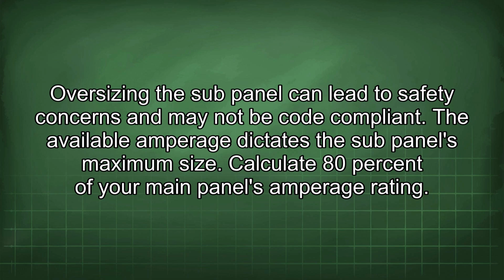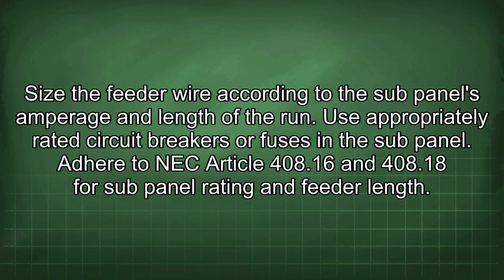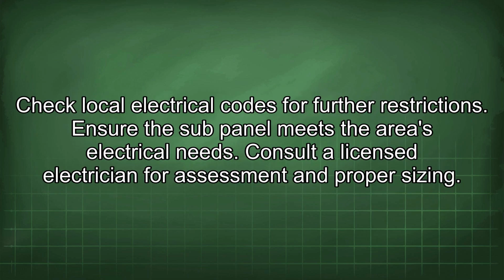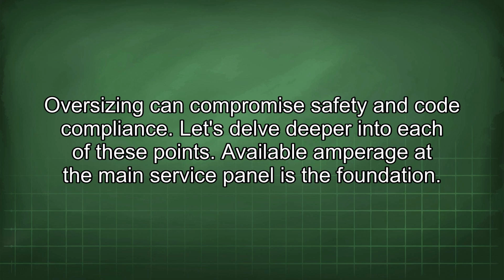The available amperage dictates the sub-panel's maximum size. Calculate 80% of your main panel's amperage rating. Size the feeder wire according to the sub-panel's amperage and length of the run. Use appropriately rated circuit breakers or fuses in the sub-panel. Adhere to NEC Article 408.16 and 408.18 for sub-panel rating and feeder length. Check local electrical codes for further restrictions. Ensure the sub-panel meets the area's electrical needs. Consult a licensed electrician for assessment and proper sizing. Oversizing can compromise safety and code compliance. Let's delve deeper into each of these points.